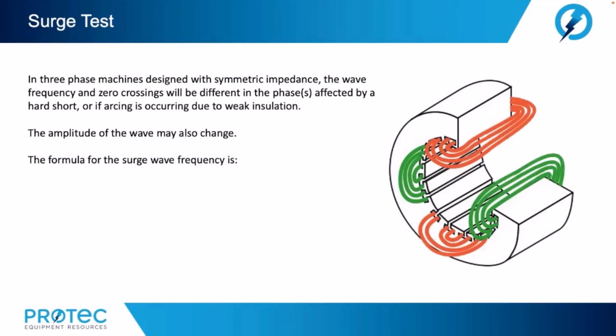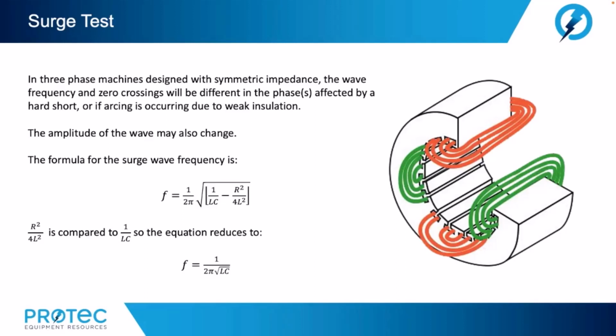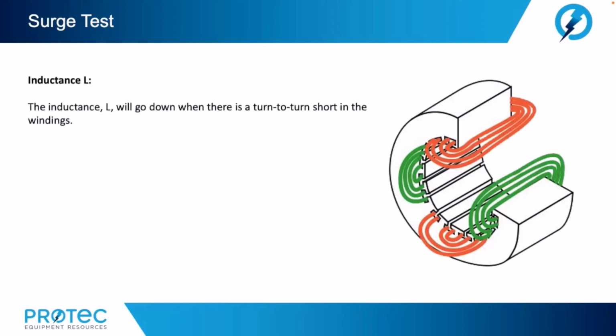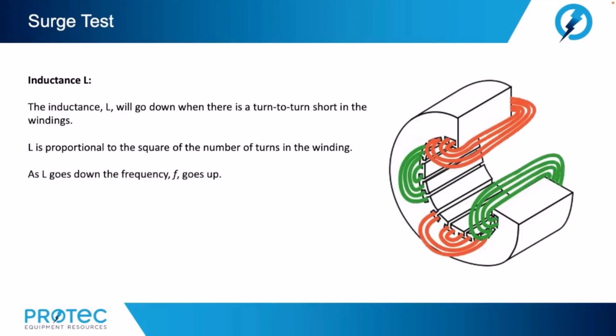The formula for the surge wave frequency is: frequency equals 1 divided by 2 pi times the square root of (1 divided by LC minus R squared divided by 4L squared). Now, R squared divided by 4L squared is small compared to 1 over LC. So the equation reduces to frequency equals 1 divided by 2 pi times the square root of LC. Let's look at inductance. The inductance will go down when there is a turn-to-turn short in the windings. Inductance is proportional to the square of the number of turns in the winding. As inductance goes down, the frequency goes up. An increase in frequency shifts the wave's zero crossing to the left on the surge test screen.